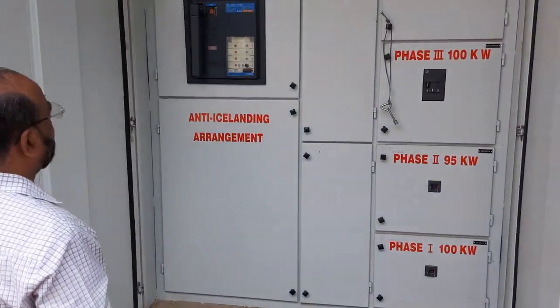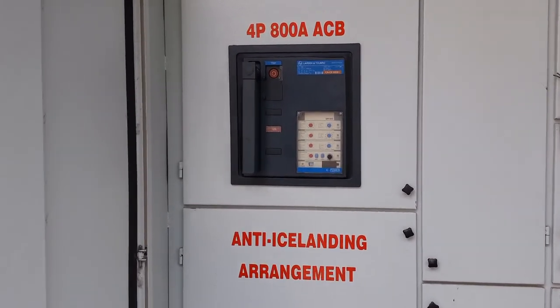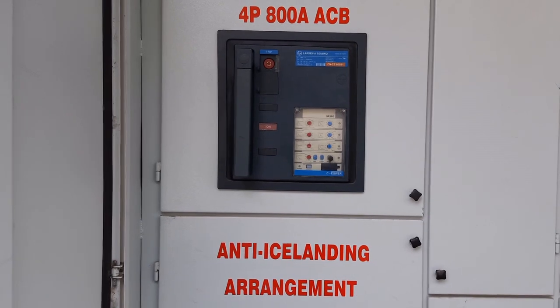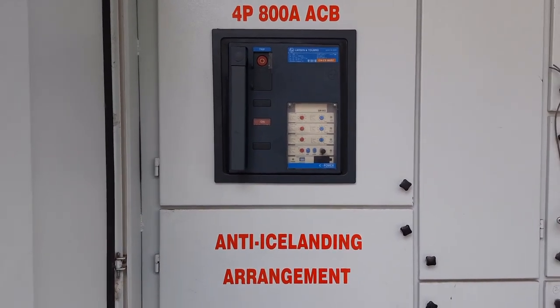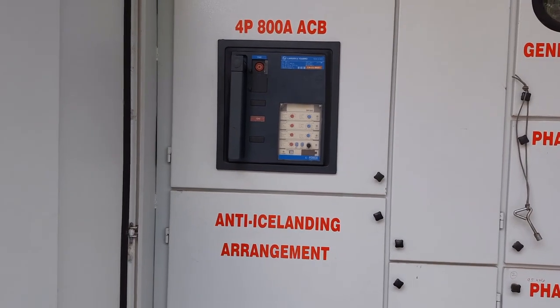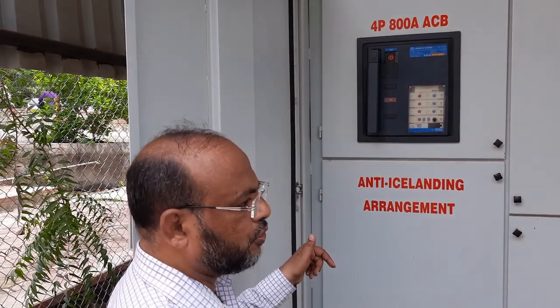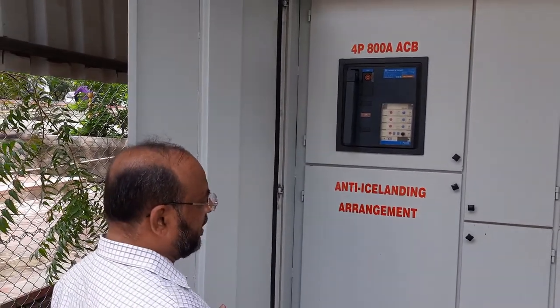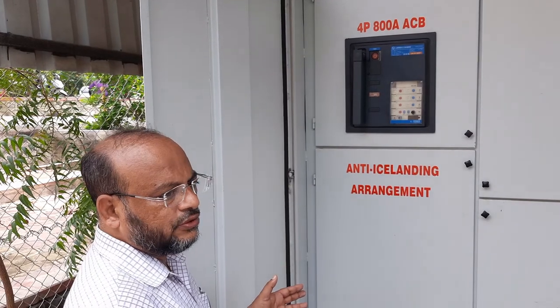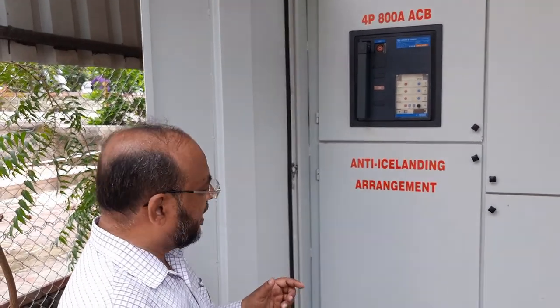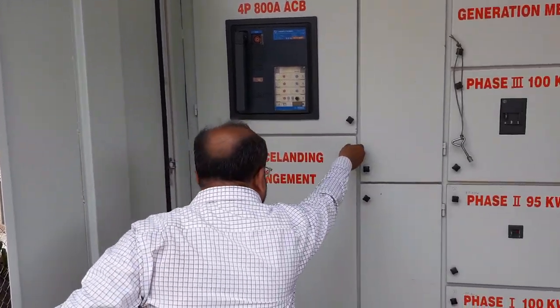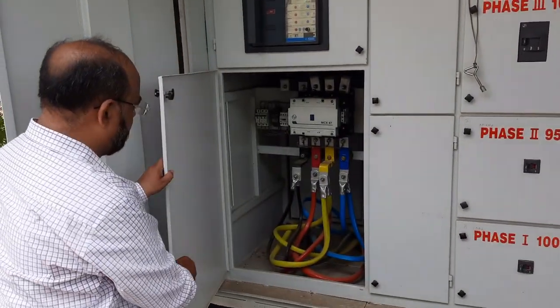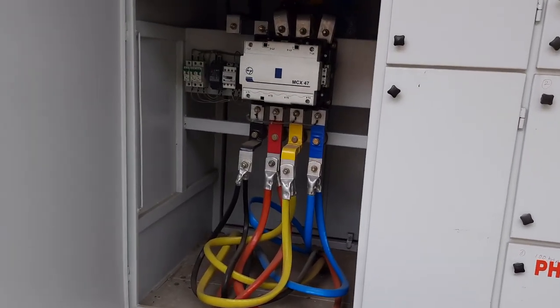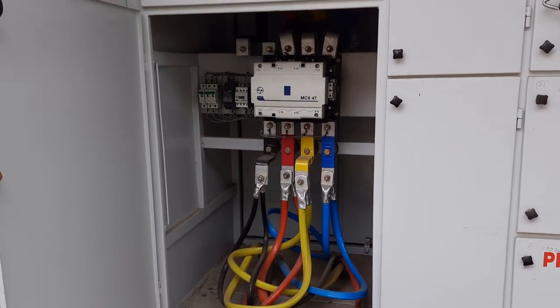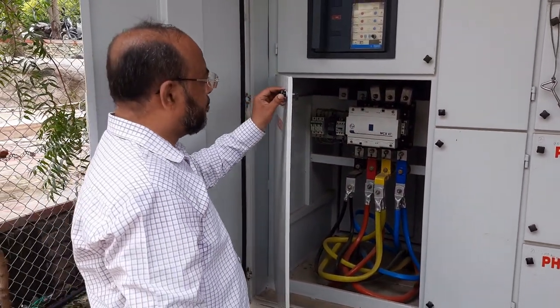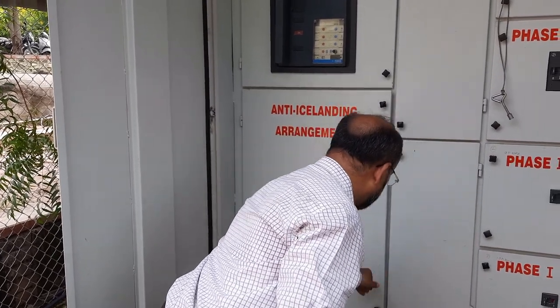This panel comprises an 800 ampere ACB, air circuit breaker, which is the LT circuit breaker, and an anti-islanding switch arrangement. The purpose of the anti-islanding switch is that if single phasing occurs, our entire system should be switched off. So it is one more safety measure, no doubt. An inbuilt islanding switch is there in the inverters, but an additional islanding switch has been installed as per the direction of MSEDCL and the state electricity regulation. So it gives a second layer of protection to the people as well as the property and electrical installation in the campus.